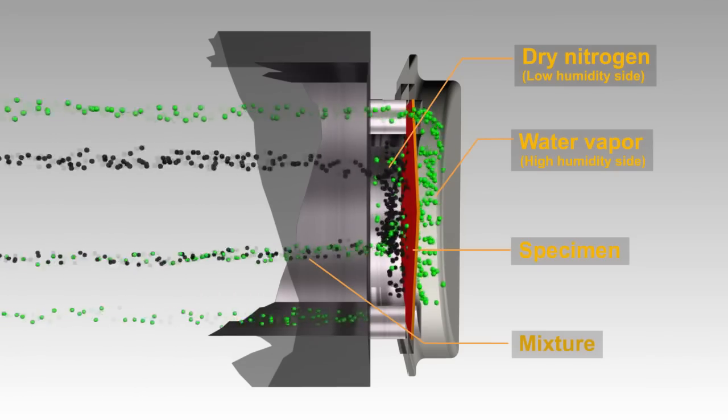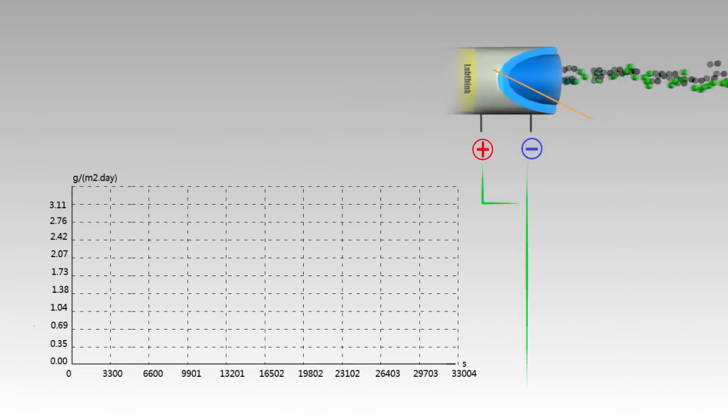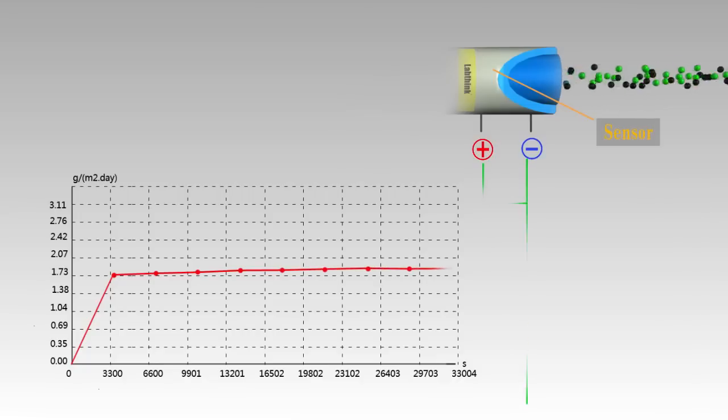The diffused water vapor molecules enter into the electrolytic sensor and electrolyze with phosphorus pentoxide proportional current, based on which the water vapor transmission rate is obtained by analyzing the electrical signal.